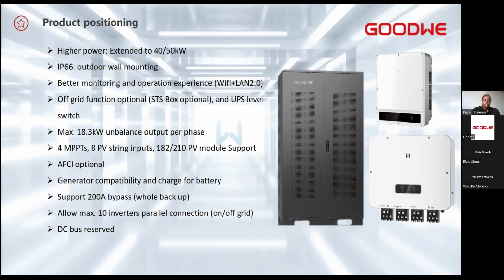And each inverter is able to utilize different orientations and different site conditions, with up to 4 MPPTs. This allows you to connect up to 8 PV strings per inverter. The MPPT is high rated, so you can utilize either the 182 mm or the 210 mm wafer-sized module. AFCI is an optional feature, so depending on your sensitivity or the insurance requirements, the AFCI can be pre-ordered and the system can be even safer.